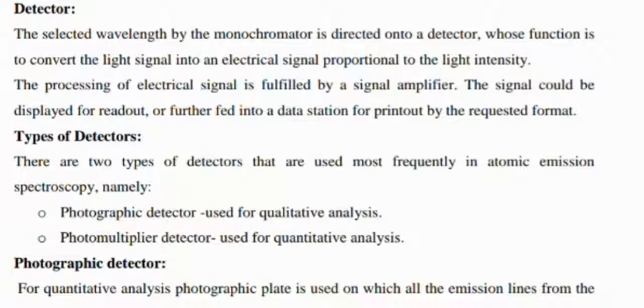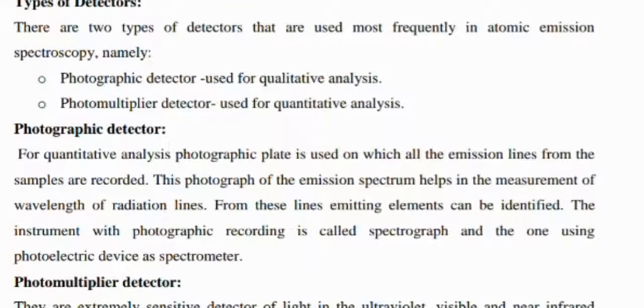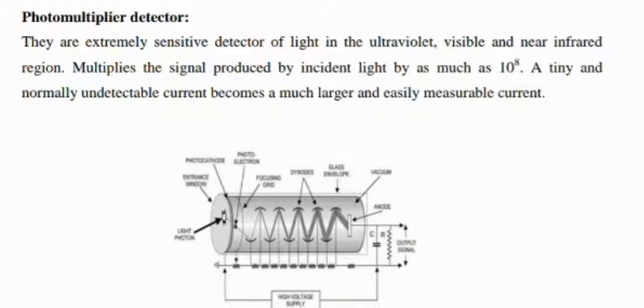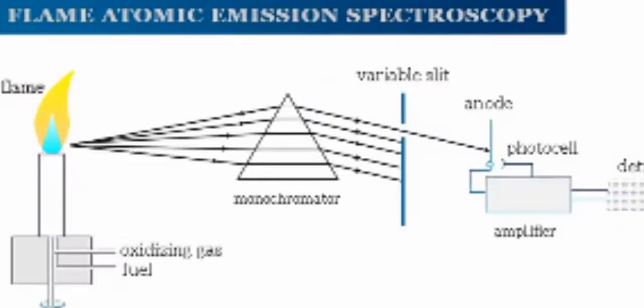It includes two types: the photographic detector for qualitative analysis, and the photomultiplier detectors for quantitative analysis. For the photographic detector, a photographic plate is used on which all the emission lines from the samples are recorded. Photomultiplier detectors are extremely sensitive detectors of light in the ultraviolet, visible, and near-infrared region with amplification of 10^8 incident light.